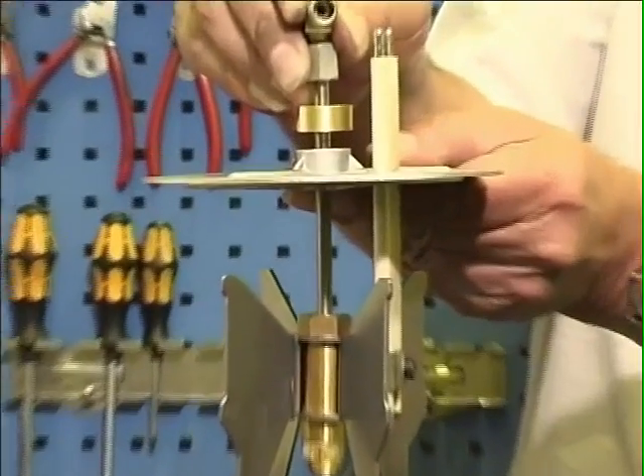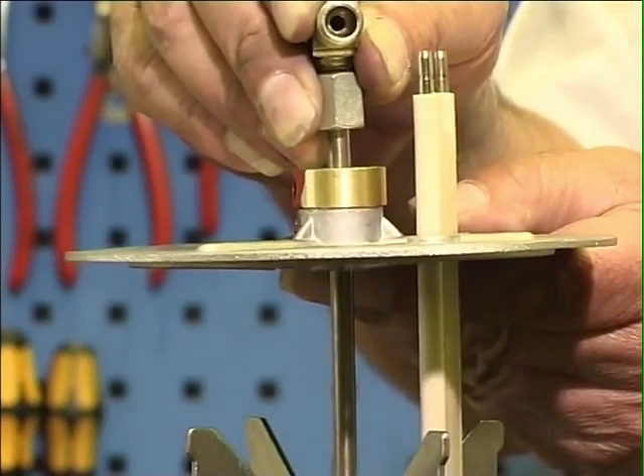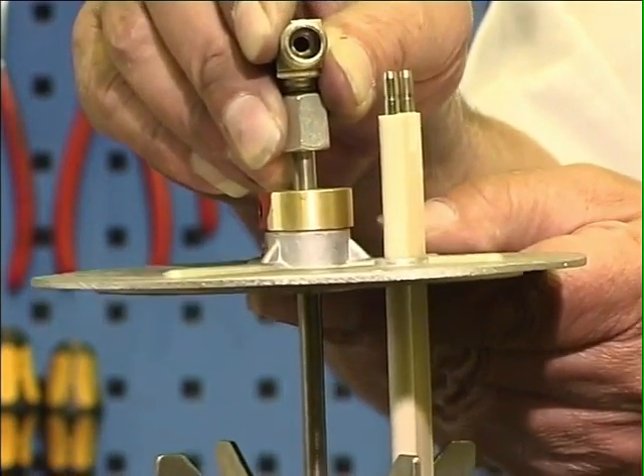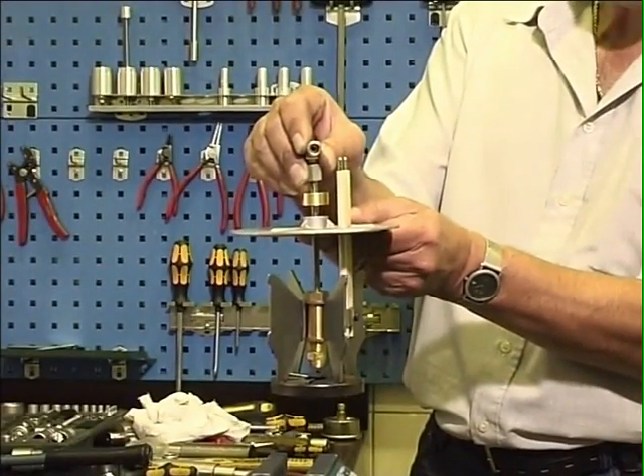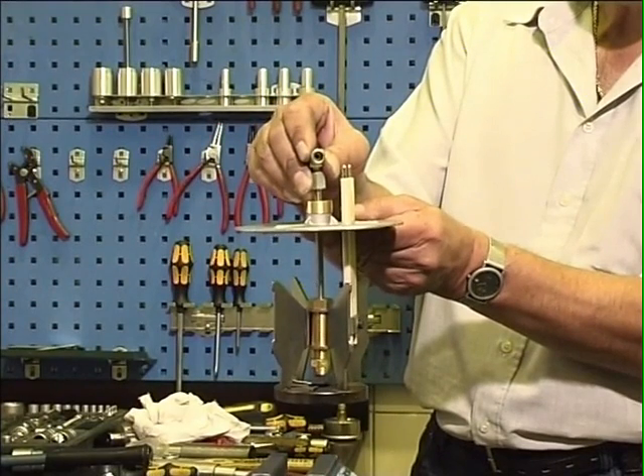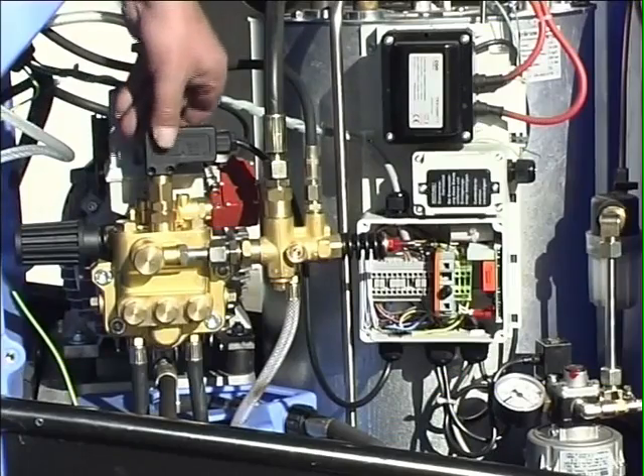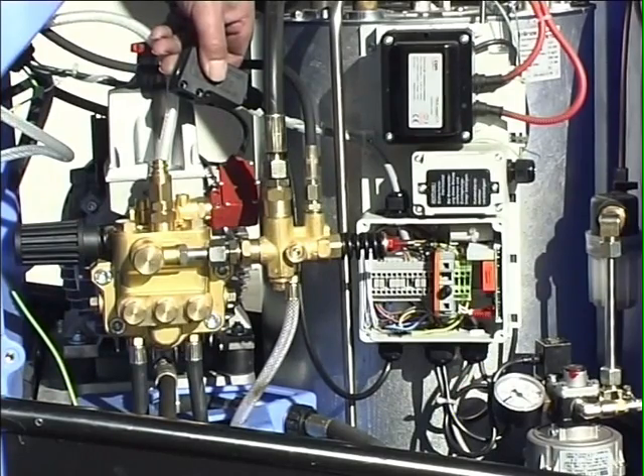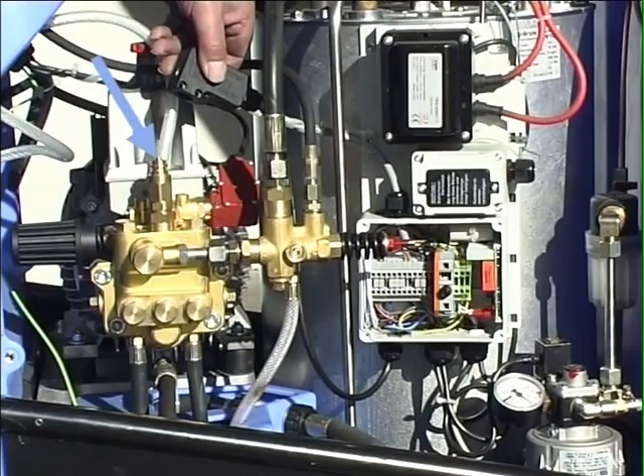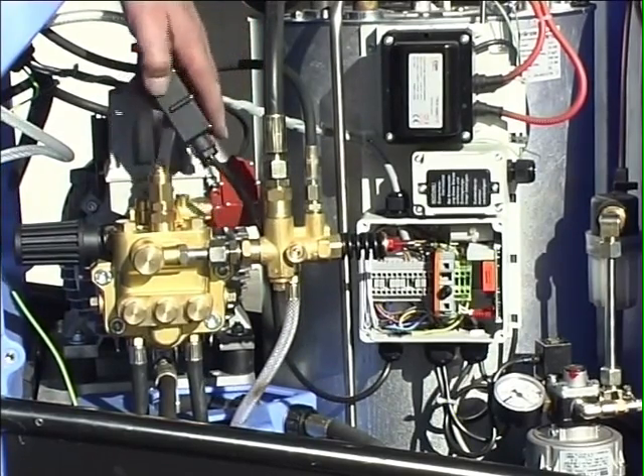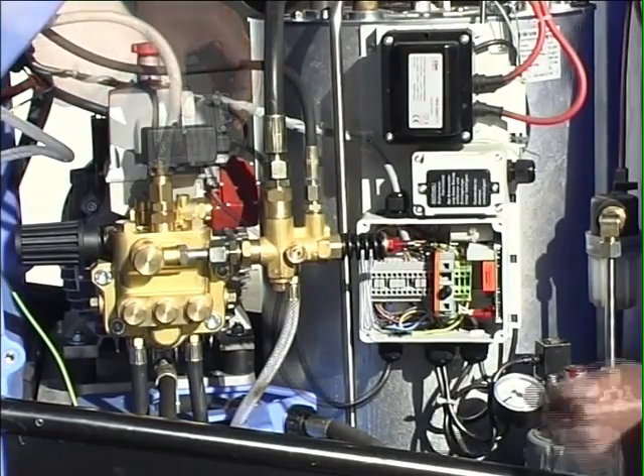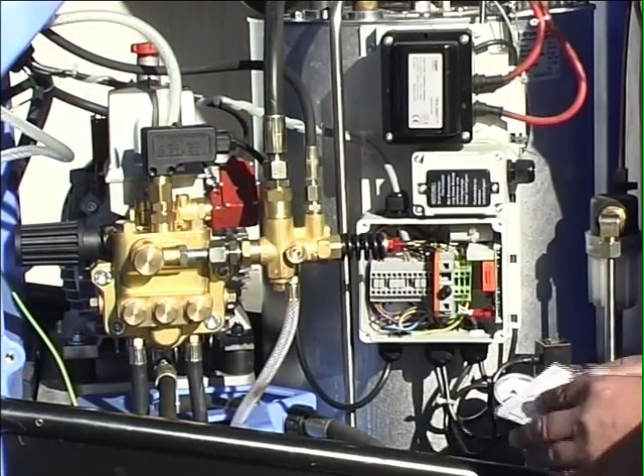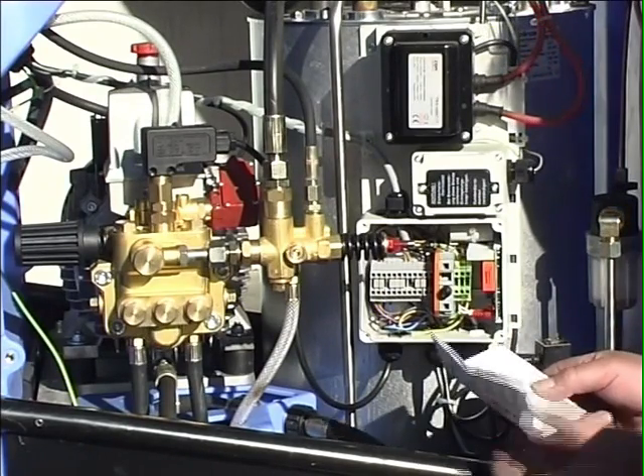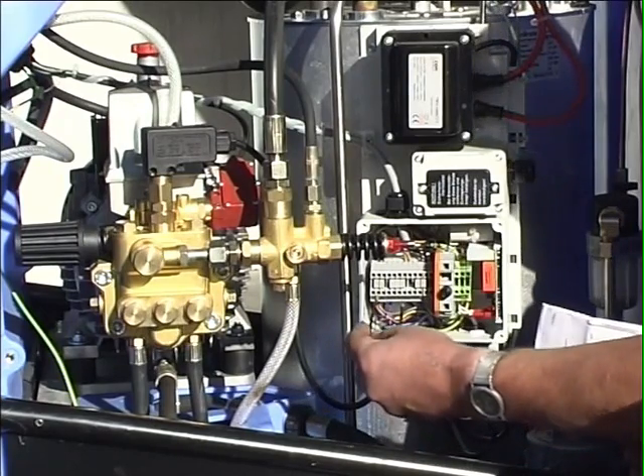On the oil supply line, you can set the air volume by sliding. This ensures optimum combustion. Pushing downward results in less air supply. Pushing upward results in more air supply. This depends on the fuel quality and the atmospheric pressure. Now, check the function of the black pressure switch, which starts the burner. For this purpose, bridge contacts 3 and 4 for the O series. There is a switching plan in the terminal box. Contacts 11 and 9 for the 5 series.